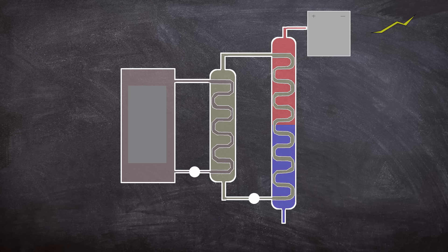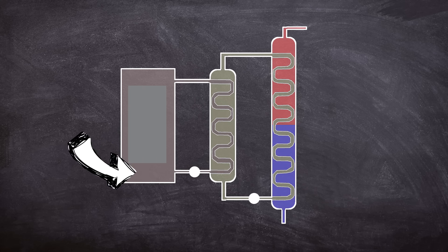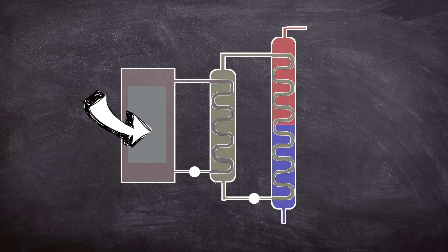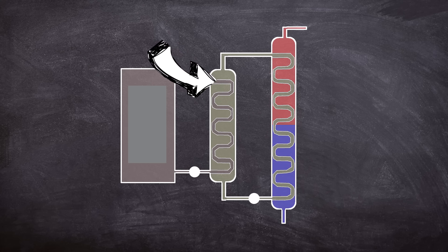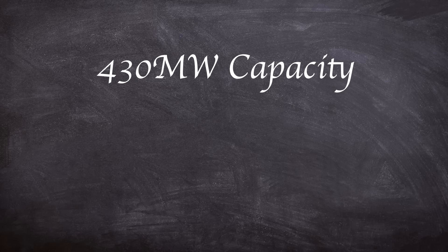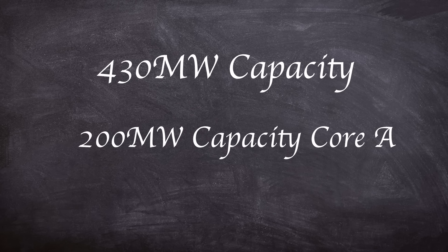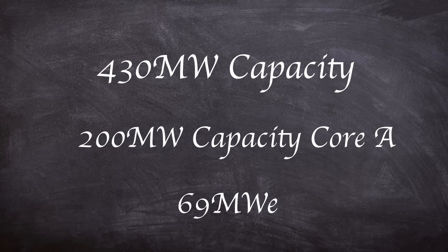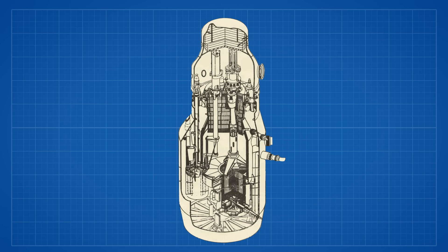The first loop passed through the reactor core and went through a heat exchanger with the secondary loop flowing through it. The heat transferred into the secondary loop and then went through a steam generator for use with a turbine for electrical power generation. The coolant flowed upward from a high-pressure plenum connected to the discharge lines of three primary sodium pumps, through the core and blanket sub-assemblies into the upper plenum, then by gravity to the intermediate heat exchangers and to the suction side of the primary pumps. The plant was designed with a 430-megawatt capacity, however the maximum reactor power with its first core loading was 200 megawatts. The reactor was capable of creating 69 megawatts of electrical power. The reactor was contained in a stainless steel vessel sealed at the top by a rotating shield plug, with the core surrounded by a blanket of depleted uranium.